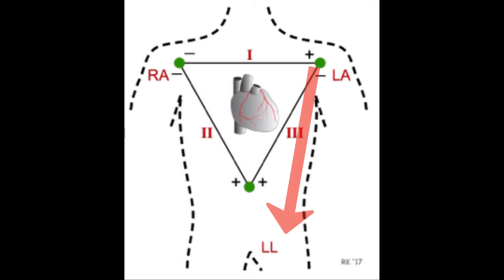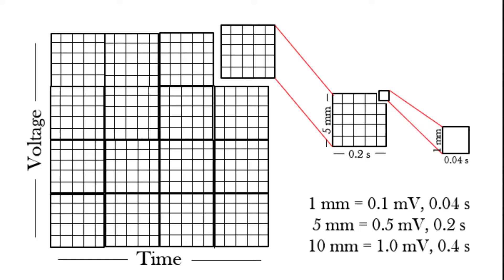Another thing to pay attention to is the machine and the paper. The ECG paper is very standardized — it leaves the machine at a constant speed of 25 millimeters per second. Each little square is one millimeter, and the big boxes are five millimeters. It's important that the machine does this accurately to get accurate representations when looking at the strip.